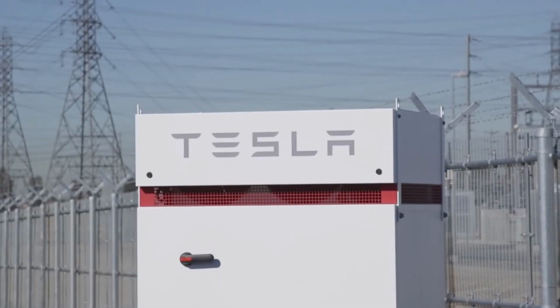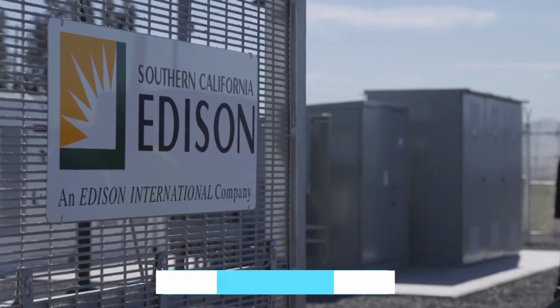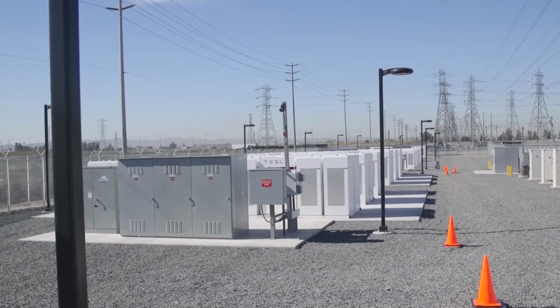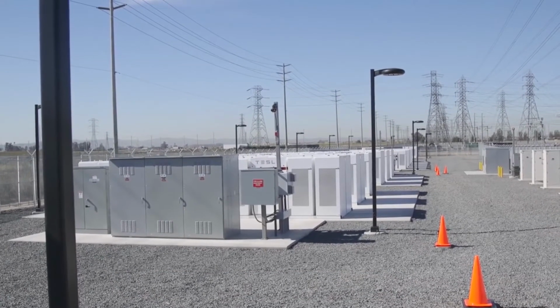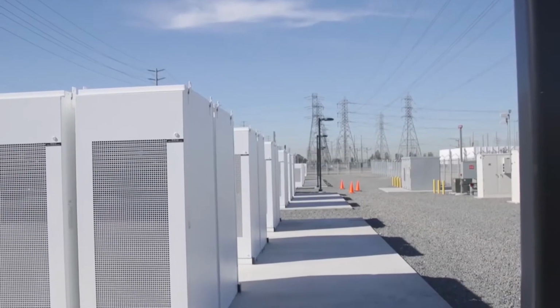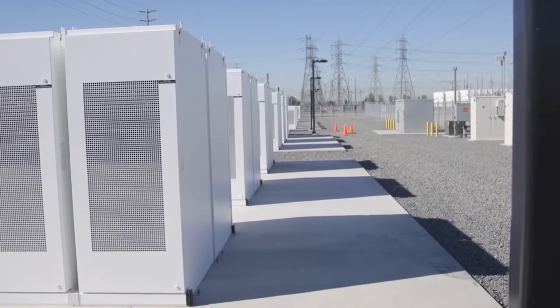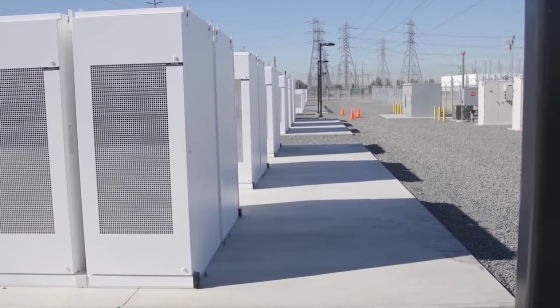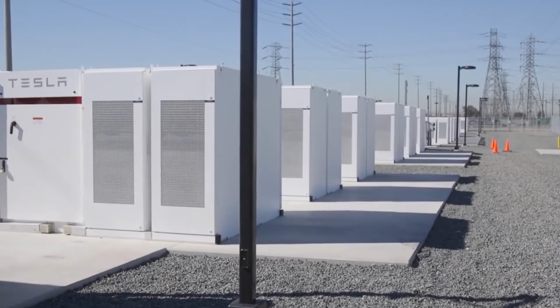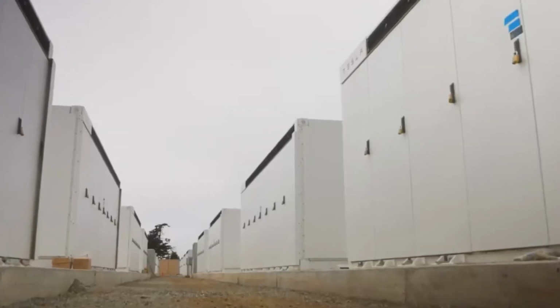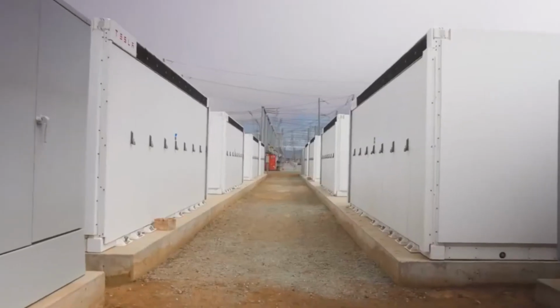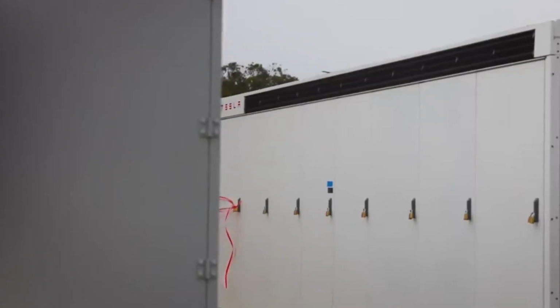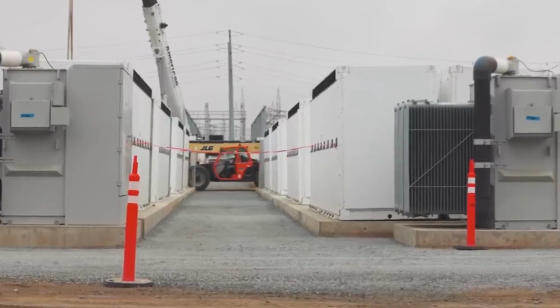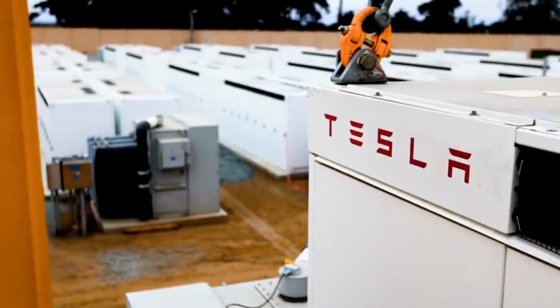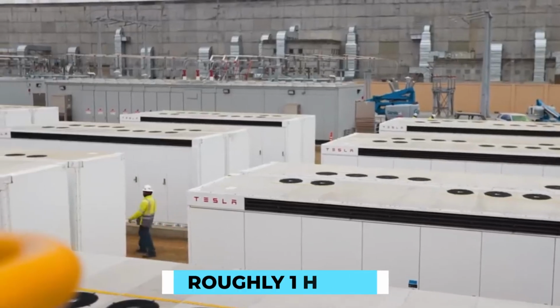Each Megapack requires maintenance once a year and once every 10 years. The annual maintenance comprises cleaning, inspections, paint touch-ups, ventilation and coolant tests, torque and calibration checks, and battery communication checks. The 10-year maintenance includes tasks like replacing the pump that powers the thermal management system, changing the door gasket, and topping off the coolant fluid. Each Megapack is anticipated to require maintenance for roughly 1 hour.